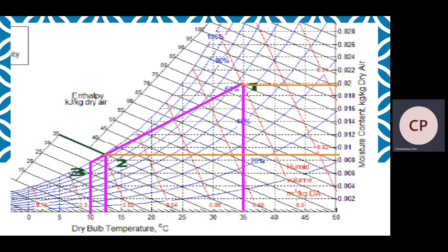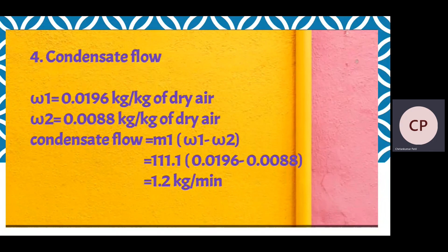Finally, we find the specific humidity at point 1 and point 2. Using orange lines extended to the moisture content axis (kg per kg of dry air): omega1 at point 1 is 0.0196 kg per kg of dry air, and omega2 at point 2 is 0.0088 kg per kg of dry air. The condensate flow is calculated as M1 multiplied by (omega1 minus omega2), giving 1.2 kg per minute.